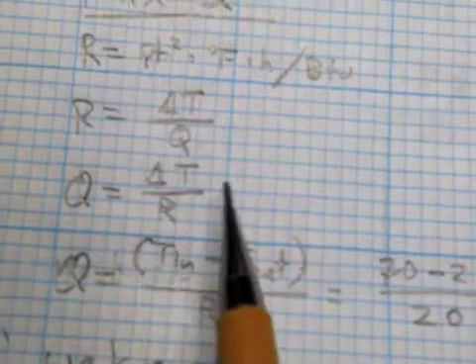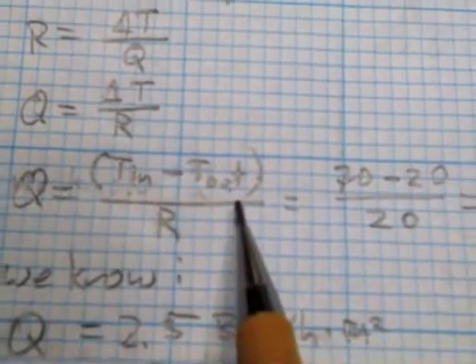We can find Q because we know ΔT — that's 70°F inside minus 20°F outside — and we know the total R-value is 20. Since R = ΔT / Q, rearranging gives Q = ΔT / R. Writing it out: Q = (70 − 20) / 20 = 50 / 20 = 2.5. So Q is 2.5 BTUs per hour per square foot.